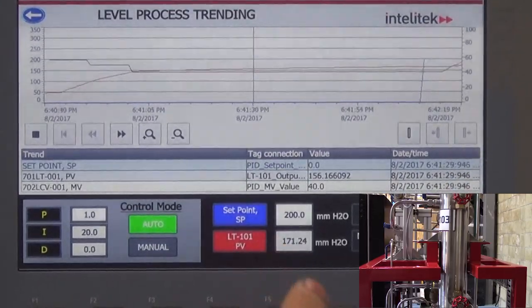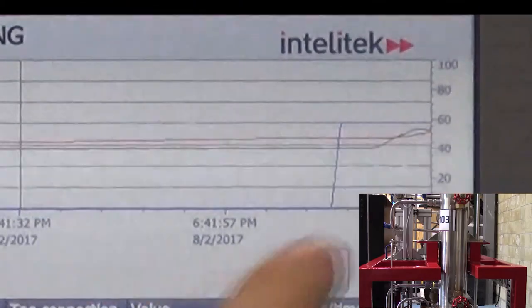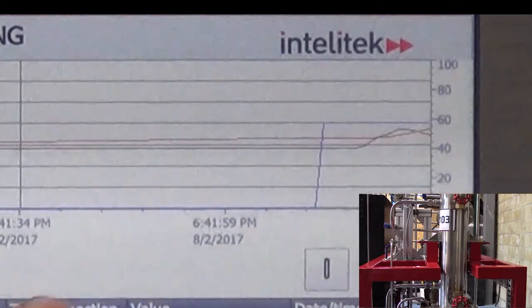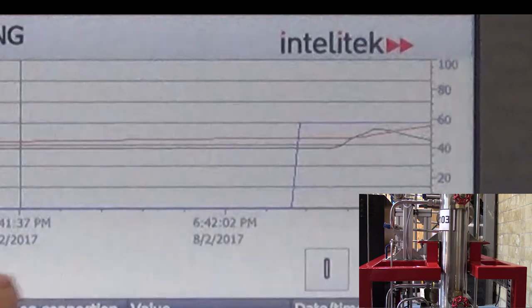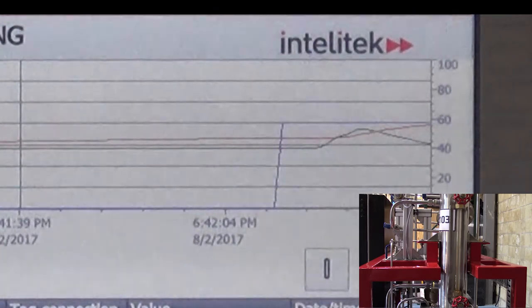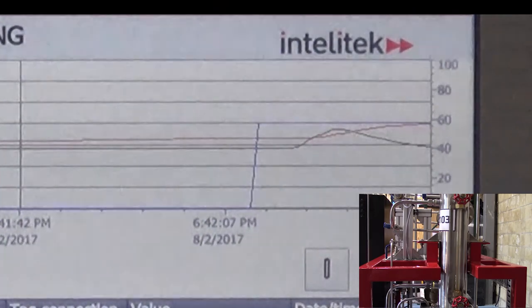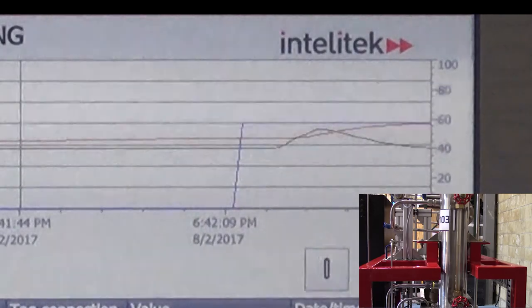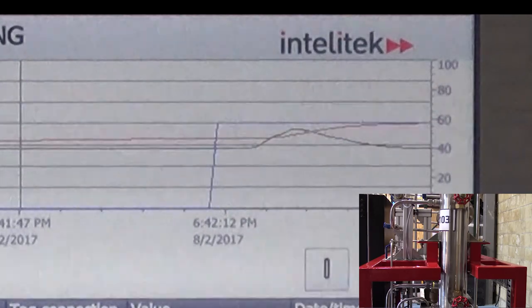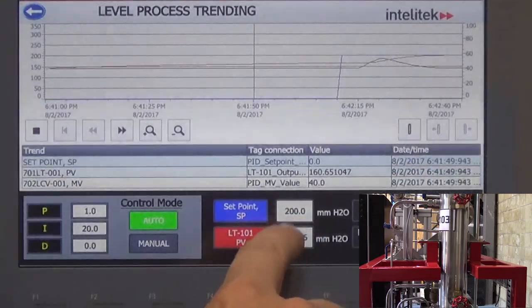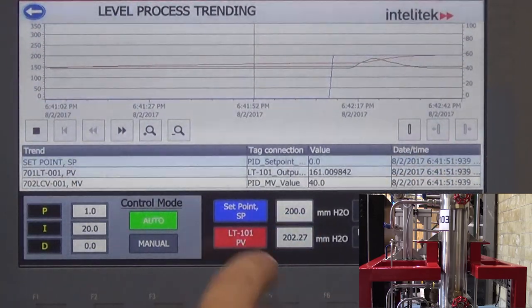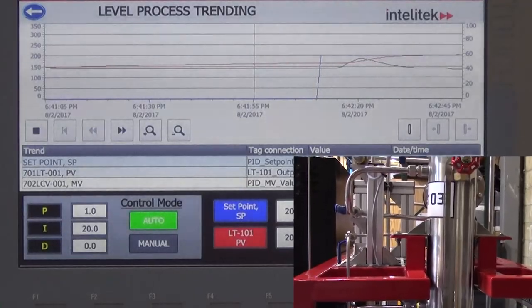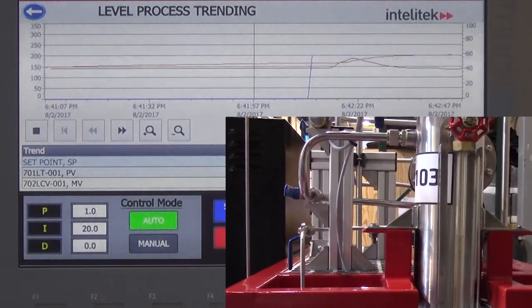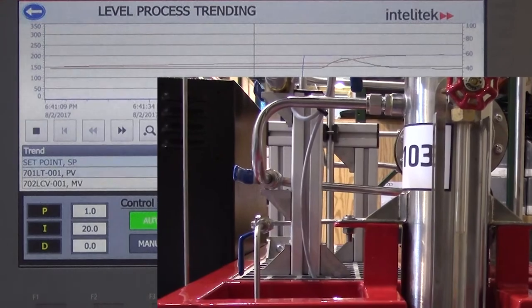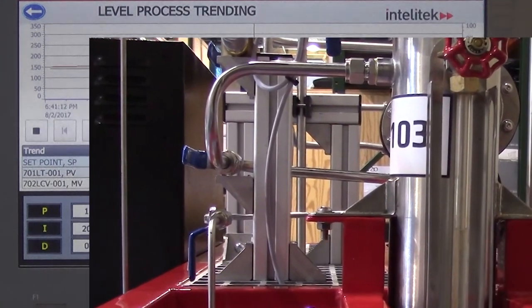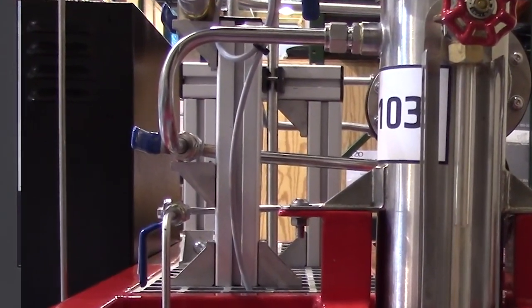And you can see on the chart, we have a black line representing where we're actually at. We have a red line representing the target of where we want to go. And as the system's building up, you can see it came up to 200.2. And if you look at the sight glass, it will show how much water is in the unit at the time in relationship to the value of 200 millimeters of H2O.